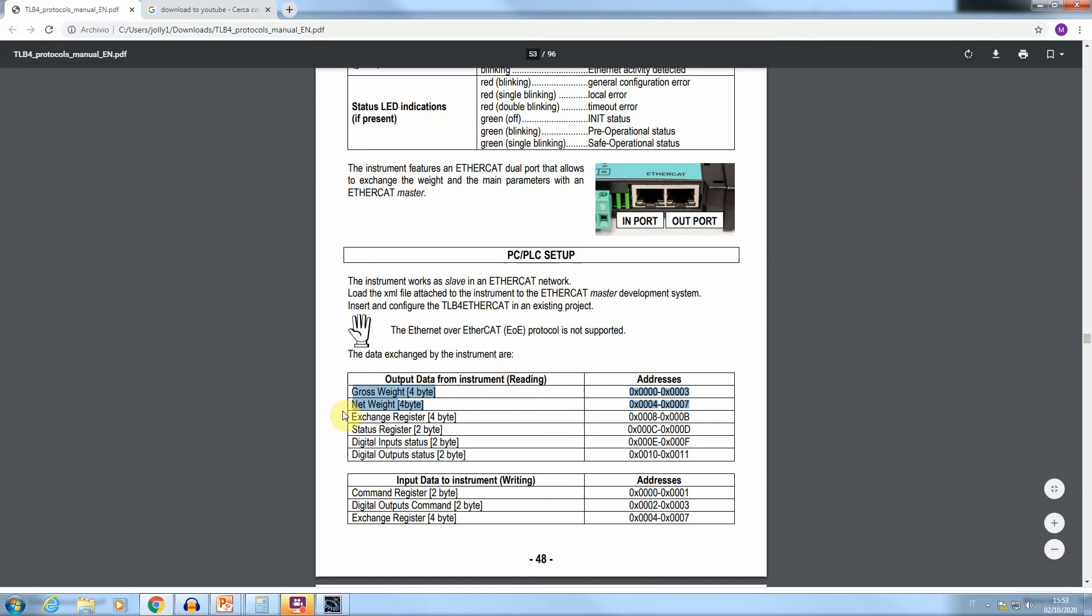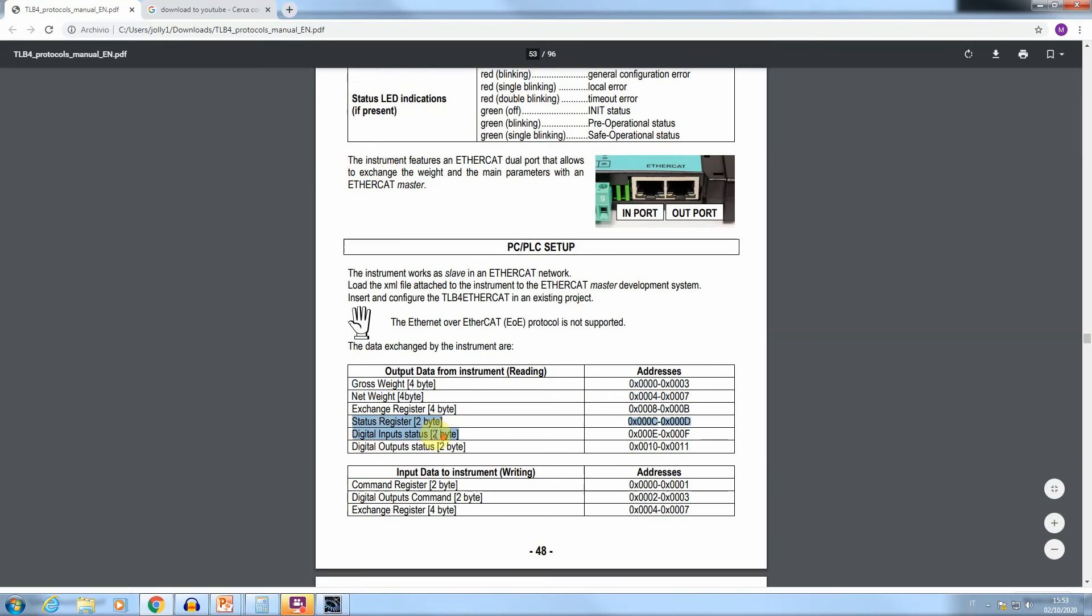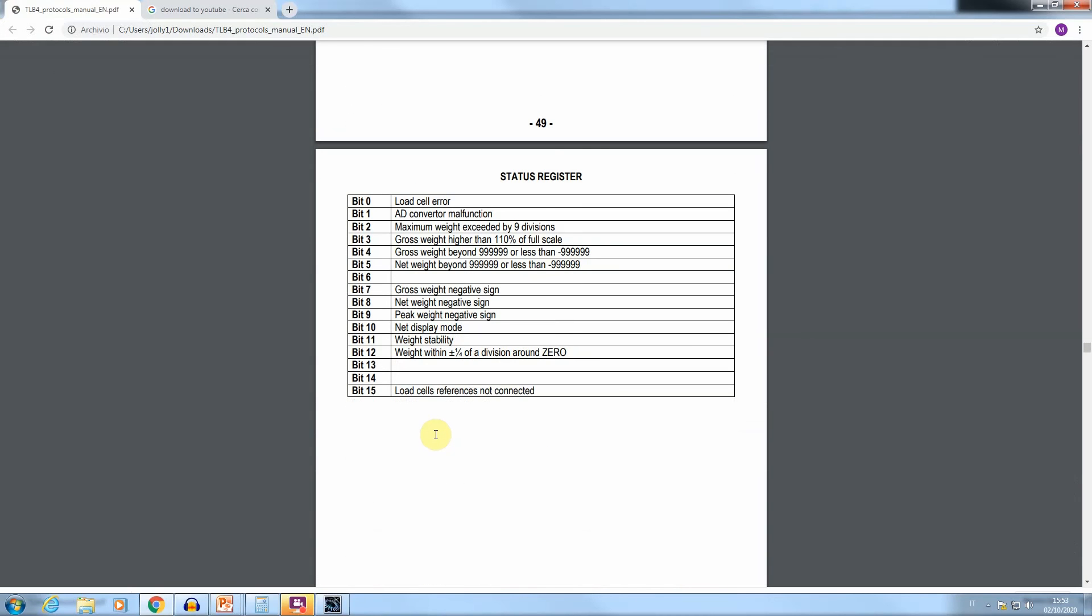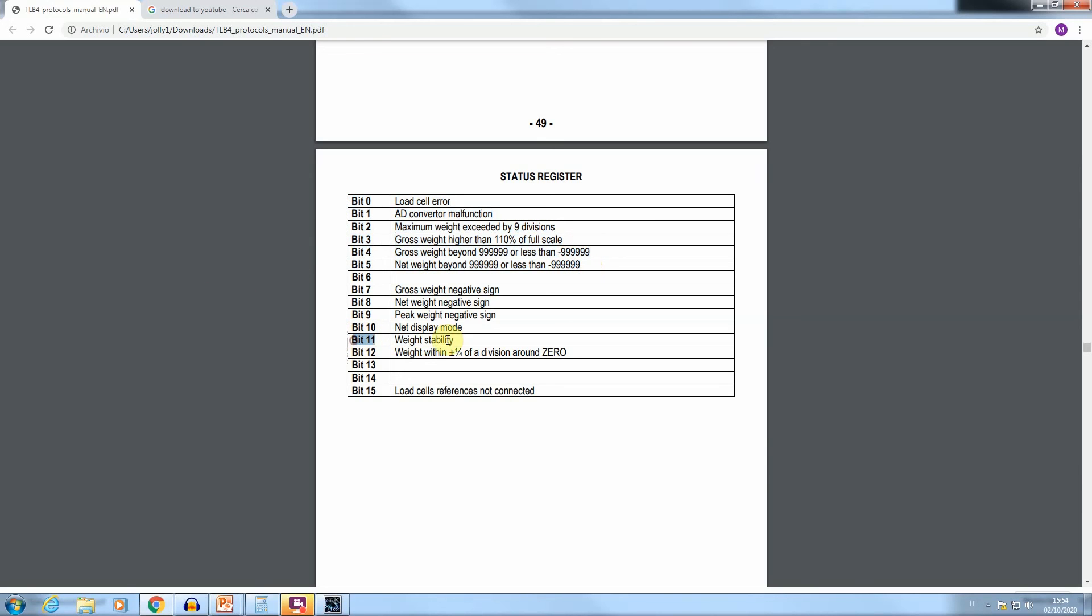The weight values assigned information is available in the status register bits. A specific table reports the meaning of each of the 16 bits forming this field. More specifically, when equal to value 1, the bit 7 signals a negative value for the gross weight, while the bit 8 signals a negative value for the net weight.